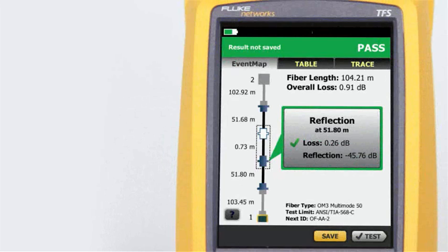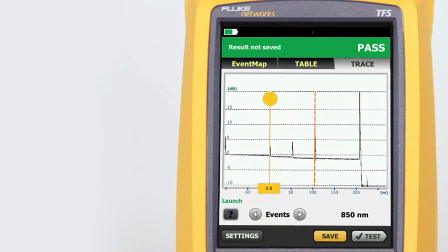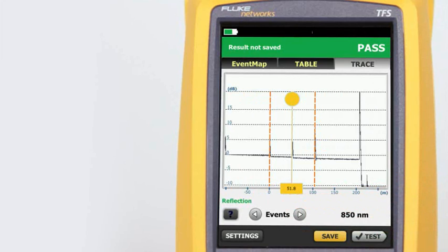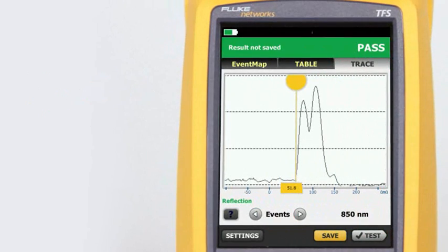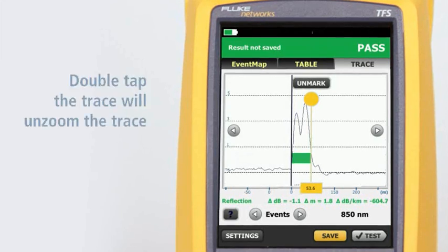Most OTDRs are designed for a myriad of applications, causing the user interface to be difficult to navigate and interpret. OptiFiber Pro combines the latest gesture-based interface technology with a capacitive touch screen to deliver the most innovative and user-friendly OTDR. To illustrate, we'll tap Trace. The trace itself should look familiar to experienced users, but both novice and experienced users will admire the advancements in ease of trace manipulation. Tapping the arrow next to Events will move the cursor to the next event on the trace. Using a reverse pinch gesture will zoom the trace at the location centered between the two fingers. Dragging a finger across the screen moves the trace in the direction of the finger drag so that events of interest may be centered. Tapping the yellow bubble on the cursor activates the fine positioning arrows and the Mark button. The Mark button sets the marker, and dragging the cursor allows manual measurements to be made with the cursor readout at the bottom of the trace. Double tapping the trace will unzoom the trace.